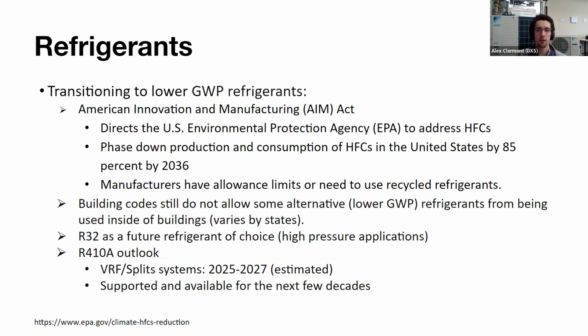So manufacturers need to either use recycled refrigerant or use some of the allowance limits provided to them. And this started as of January of this year. Unfortunately, there's a bit of a loophole with anything that's not manufactured in the US. It doesn't fall under this, and unfortunately this handcuffs American-based manufacturers a little bit. That loophole is currently being looked into.